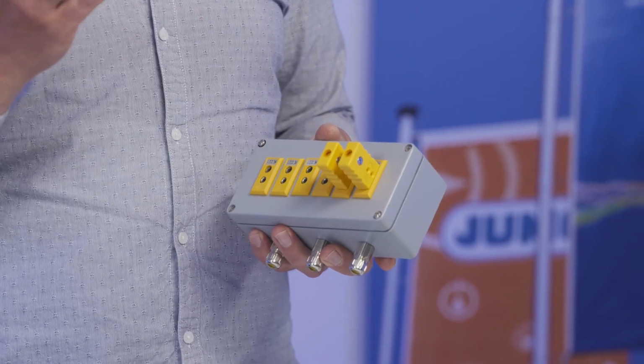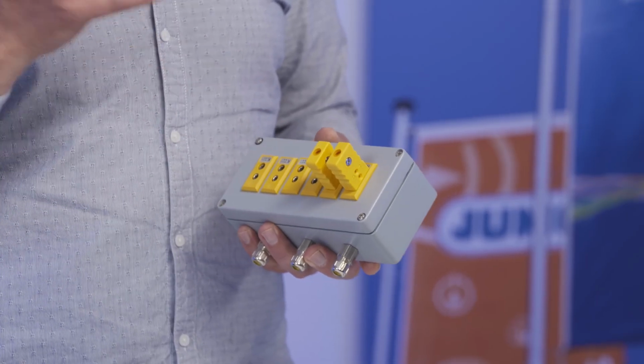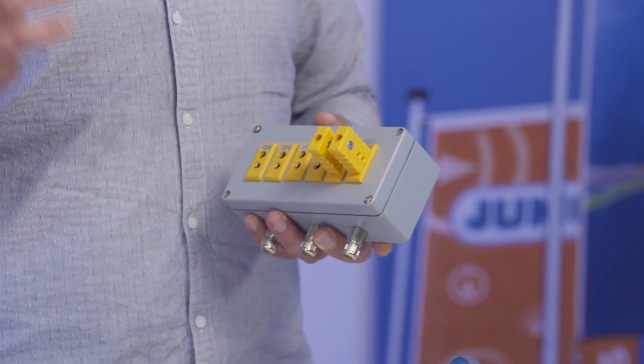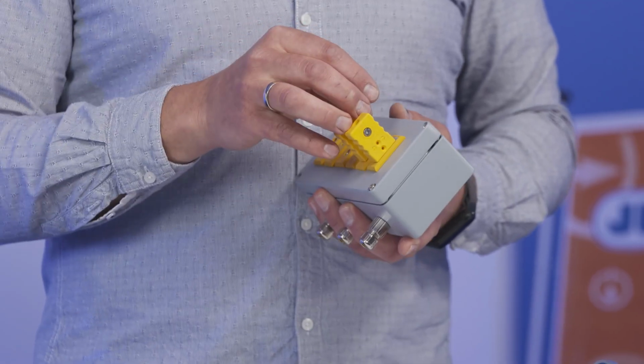Awesome, perfect. When it comes to instrumentation testing, what are typical errors or problems you encounter while you do the testing? There is always the problem with the connection between the temperature sensor and the controller or the display device. So it's better to use our thermobox, because then we have the right connection between the sensor and the controller, and it's easier to connect the device for the instrumentation tests. And you also have no problems when you use a calibrator to put in the values.